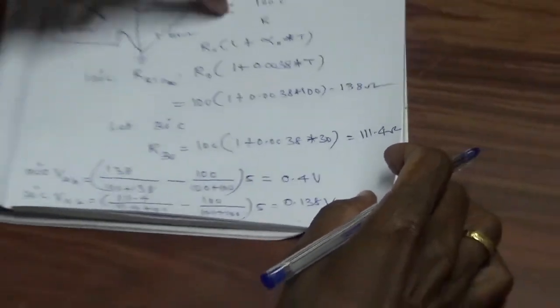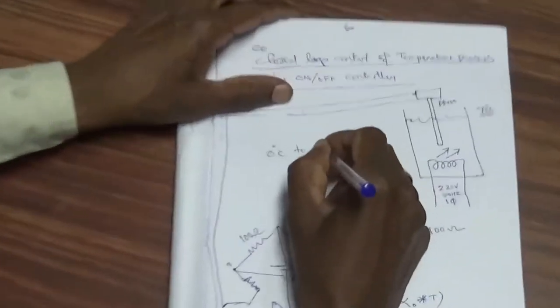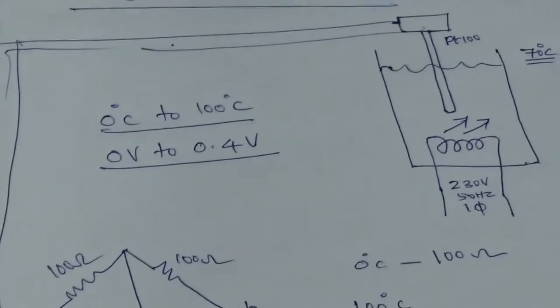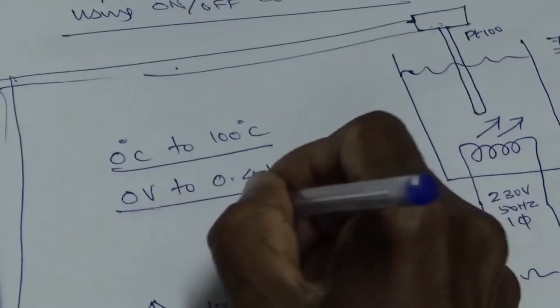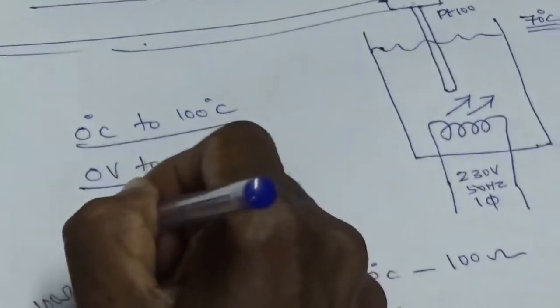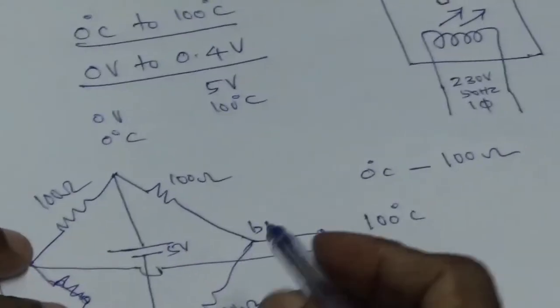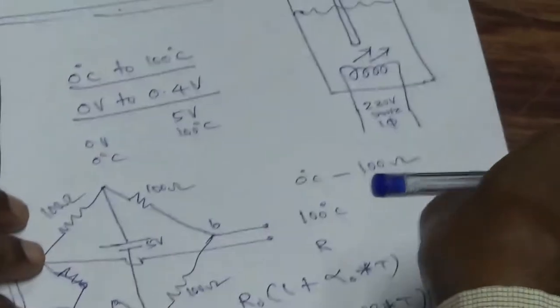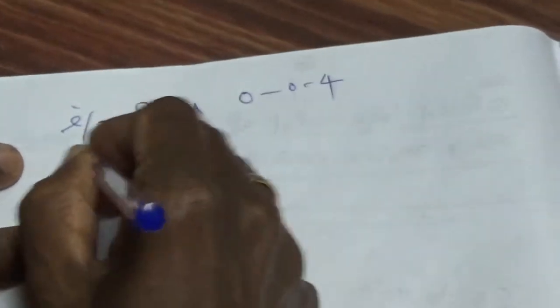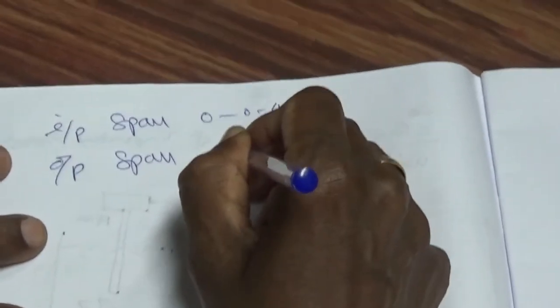Let us design a transmitter for the range of 0 to 100 degrees centigrade. At 0 degrees centigrade the output of the bridge is 0 volts, therefore the bridge output varies from 0 volt to 0.4 volt. Let us design a transmitter which will give 5 volts corresponding to 100 degrees centigrade and 0 volts corresponding to 0 degrees centigrade. The input span is 0 to 0.4 volts and the output span is 0 to 5 volts.